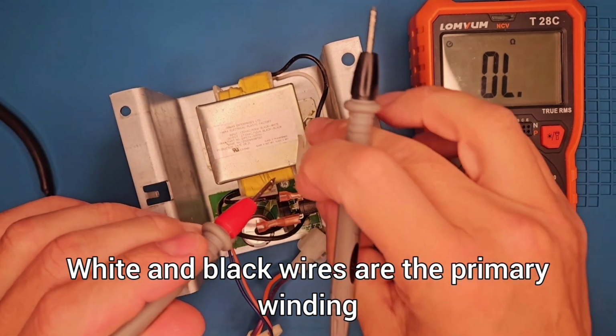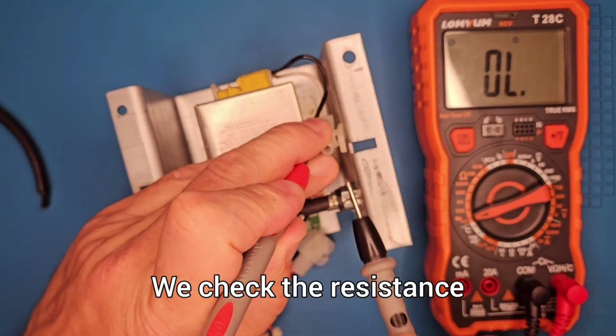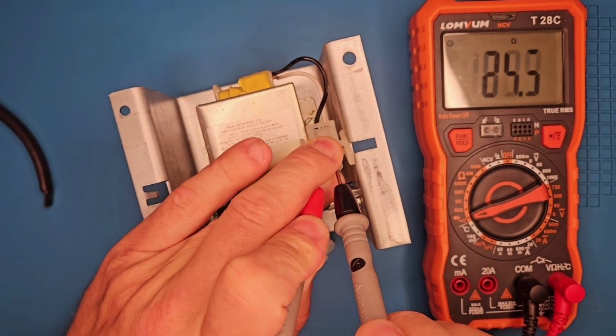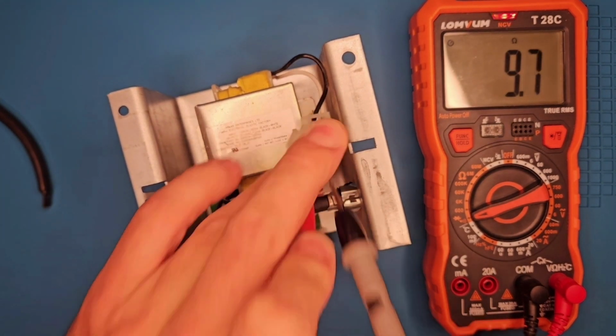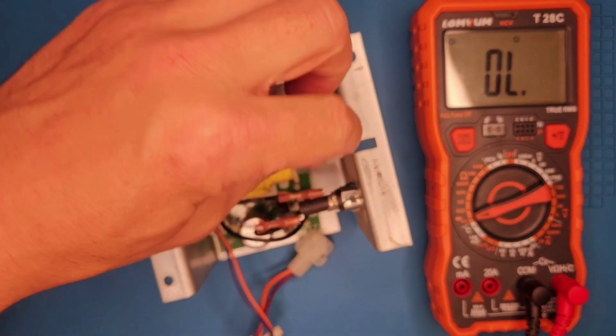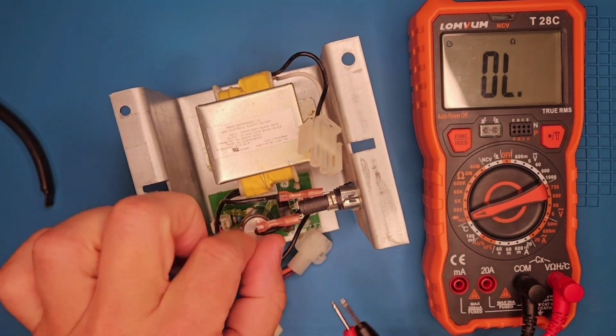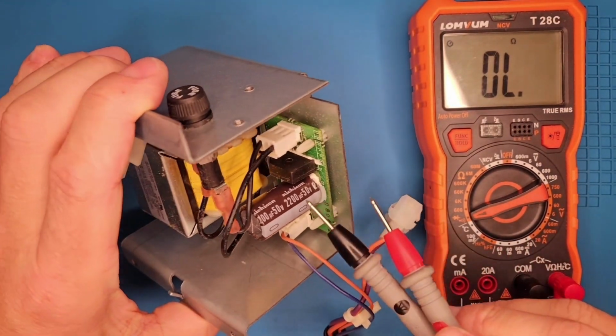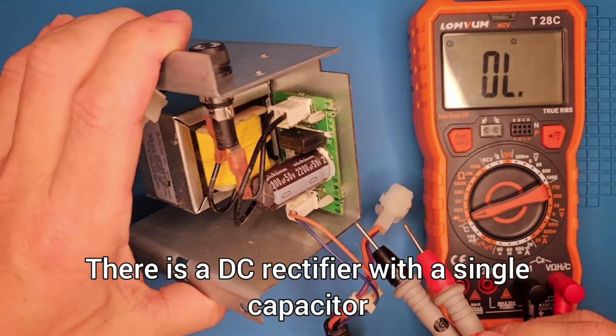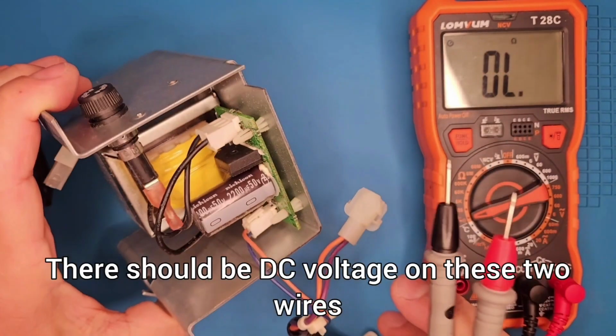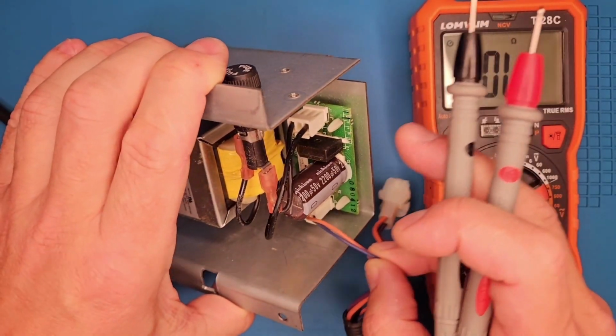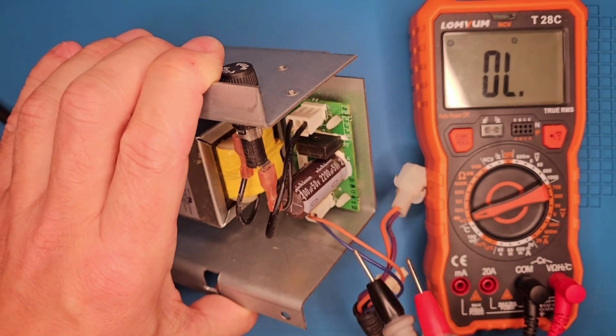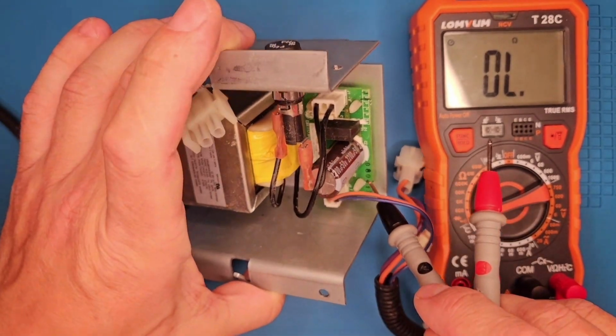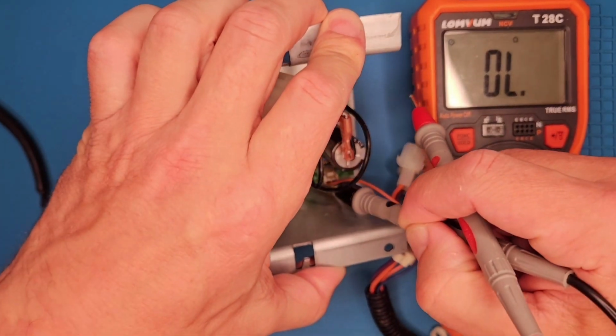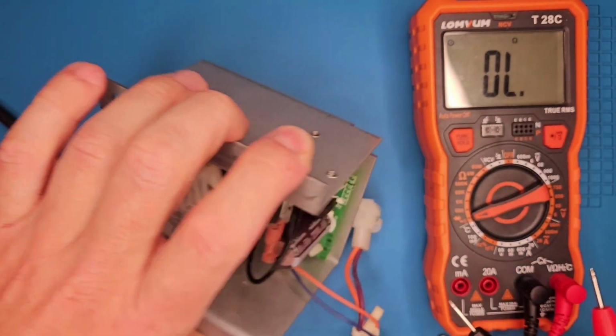White and black wires are the primary winding. We check the resistance. The reading is 10 ohms, which is normal. Next is the secondary winding. There is a DC rectifier with a single capacitor. The simplest circuit. There should be DC voltage on these two wires. There's a marking, plus and minus.